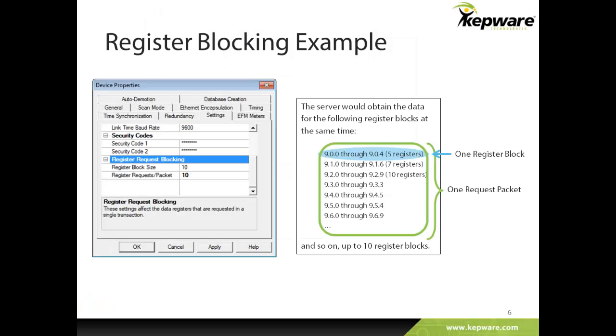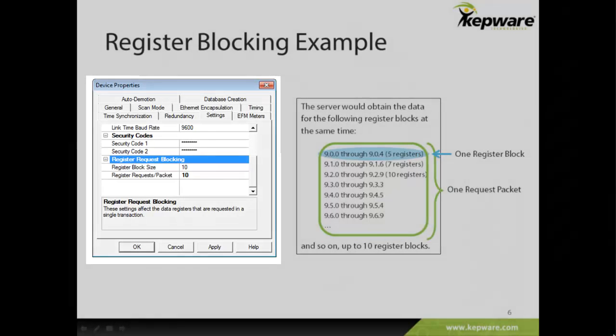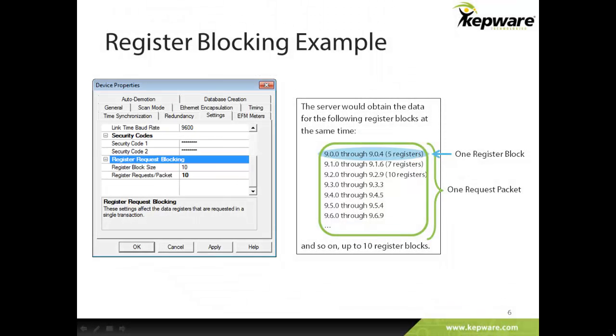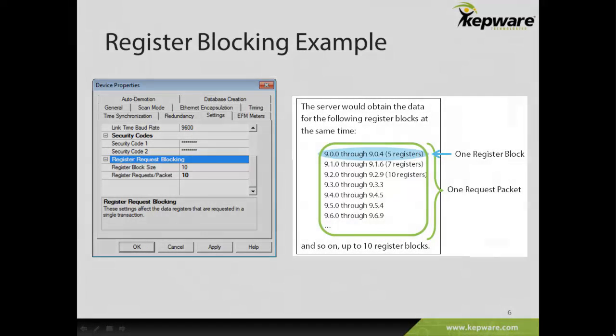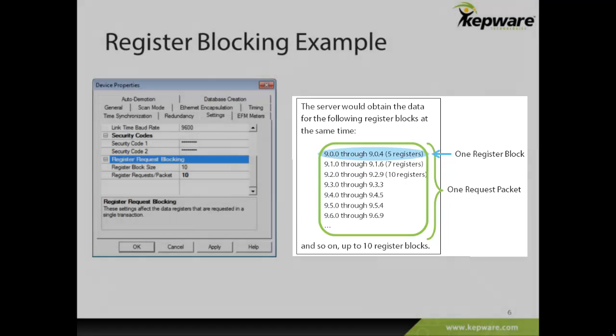In register block size, specify how many individual registers can be read in a single request. In this case, ten individual registers can make up one register block. In register request per packet, specify how many register blocks make up one packet transaction. Increasing the number of registers that can be read in a single transaction pull increases the driver data efficiency. This is useful for remote applications with communication interference issues, where more data may need to be read at one time in case of a communications loss.